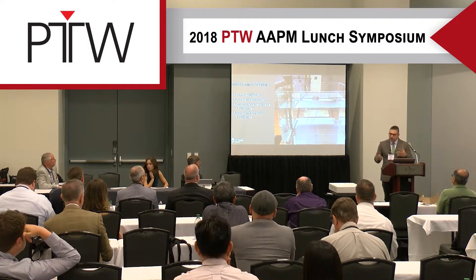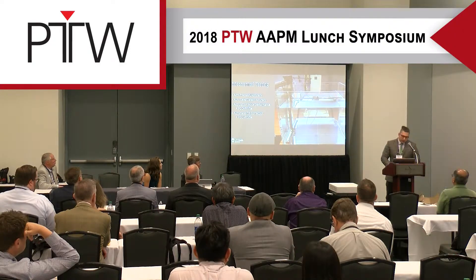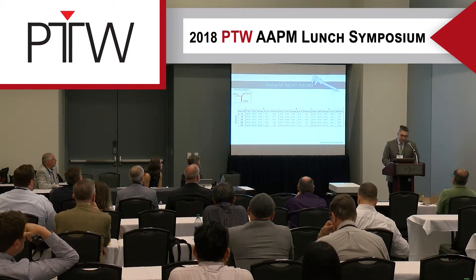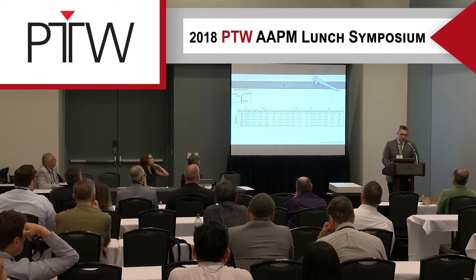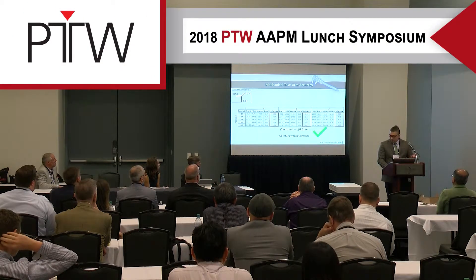For mechanical testing, I'll share highlights from around 600 measurements across precision, accuracy, auto level detection, and acquisition mode differences. For arm accuracy, we moved the arm to the origin then to 10, 20, 50, and 200 millimeters and verified with a caliper how far it actually traveled. For all measurements, the differences were sub-millimeter, and all fit within our clinic tolerance of plus or minus 0.2 millimeters — we call that an accurate system.